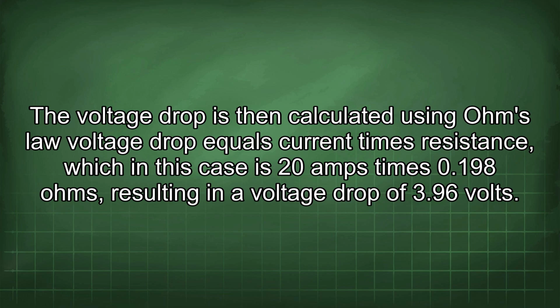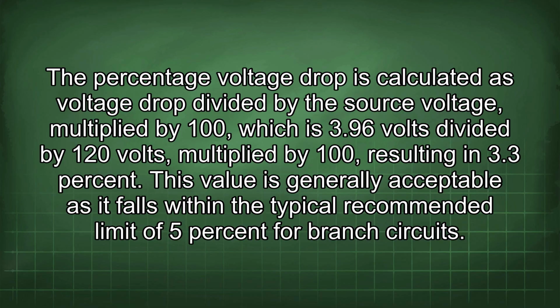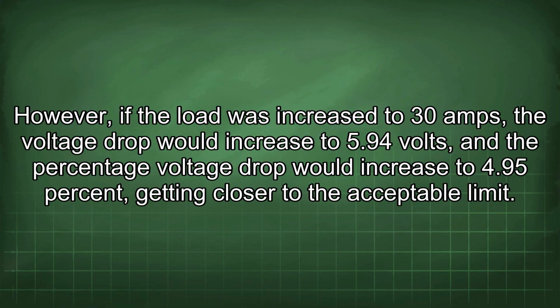drop of 3.96 volts. The percentage voltage drop is calculated as voltage drop divided by the source voltage, multiplied by 100, which is 3.96 volts divided by 120 volts, multiplied by 100, resulting in 3.3%. This value is generally acceptable as it falls within the typical recommended limit of 5% for branch circuits. However, if the load was increased to 30 amps, the voltage drop would increase to 5.94 volts, and the percentage voltage drop would increase to 4.95%, getting closer to the acceptable limit.